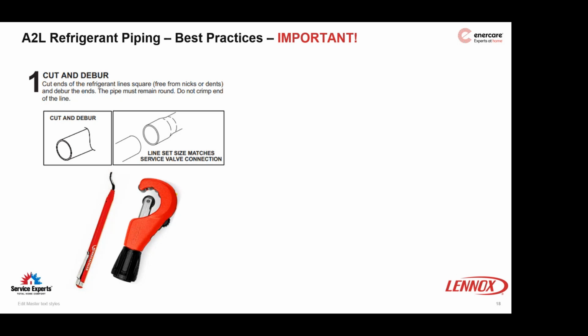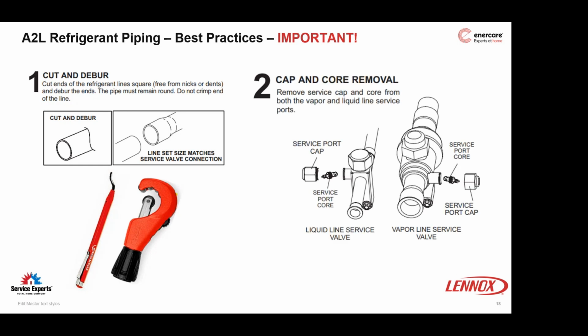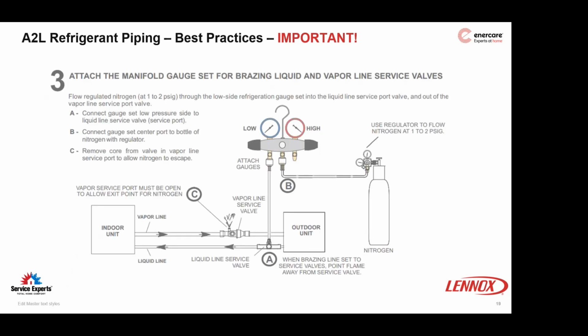But for the time being, let's make sure that we're using torches and cutting these things and applying things safely. So there you go, looking at pulling the cores out, making sure that those are out of there. I've heard stories, at least back in my older days, that these things weren't being pulled out. Sometimes the little O-rings on these service port cores get melted and they don't seal anymore. Now with a flammable refrigerant on the other side of this valve, I want to be as cautious as possible when I'm putting stuff in.